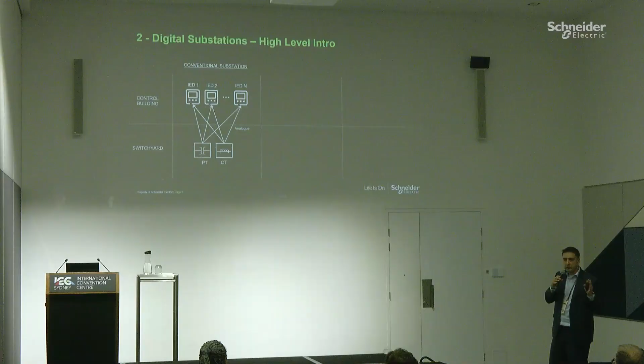I'm looking here primarily at a bigger substation, transmission level, grid level substation, where you have your PT, CT—we'll call those sensors. So you have your voltage sensors, your current sensors out in the switch yard, and then you have your IEDs, intelligent electronic devices, in the control building. These could be protection relays, RTUs, or power meters. The connection between the PTs and CTs is done via copper cabling, analog signals, and all the analog-to-digital conversion needed for substation operation happens at the device level, not centralized. Each of these devices usually communicates using a different communication protocol, and they're often from different vendors—so a bit of a mess.